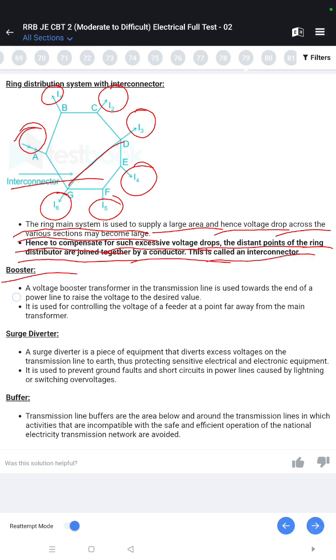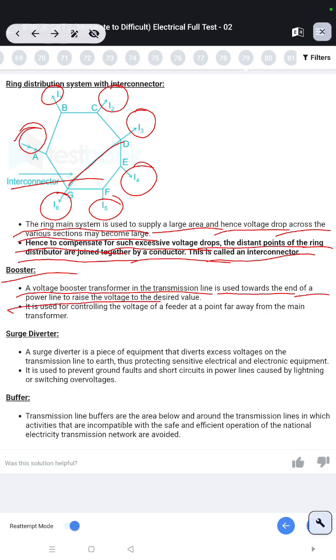A voltage booster transformer in the transmission line is used towards the end of a power line to raise the voltage to the desired value. It is used for controlling the voltage of a feeder at a point far away from the main transformer.